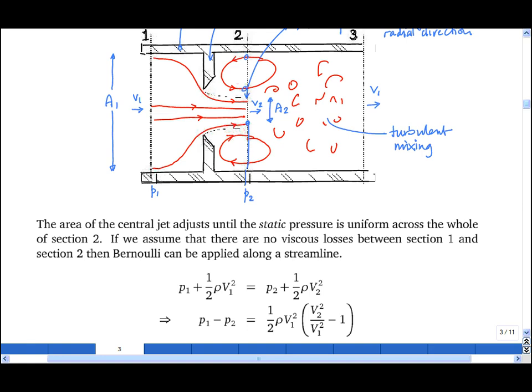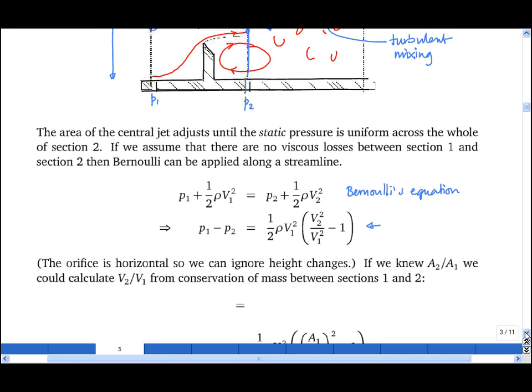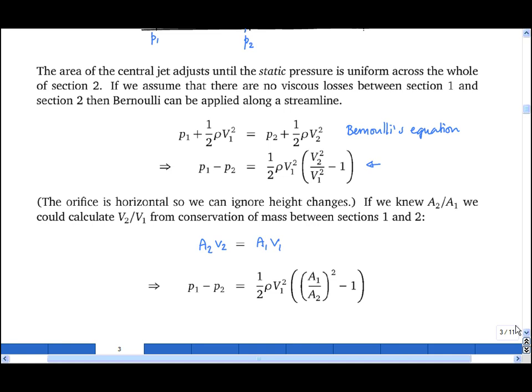If we assume that there are no viscous losses between section 1 and section 2, we can apply Bernoulli's equation between section 1 and this point on section 2. And from that we get an expression for the difference between pressure 1 and pressure 2. Now if we knew A2 and A1, we could calculate V2 over V1 from conservation of mass. As long as the density is uniform, which it is, A2V2 is equal to A1V1. And substituting that into our expression for P1 minus P2, we obtain an expression in terms of A1 over A2, and we note that this term here is a constant. It actually depends on the exact shape of the orifice.